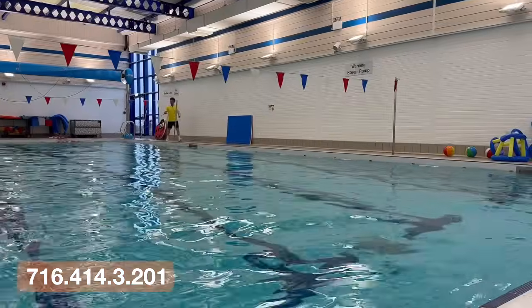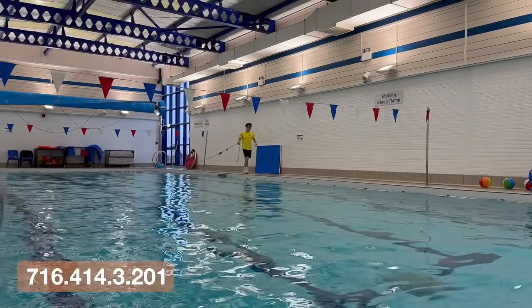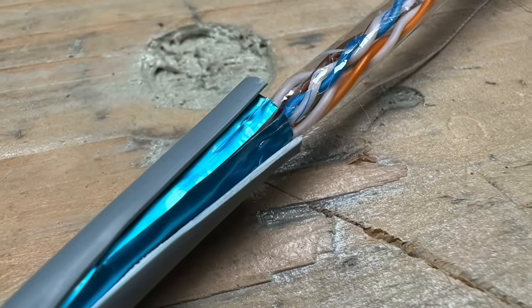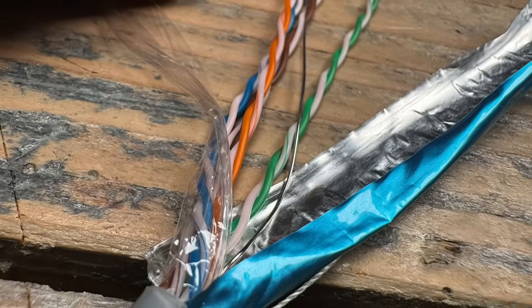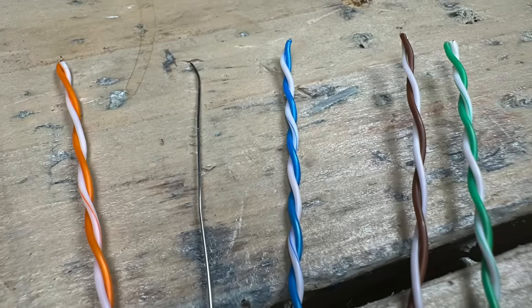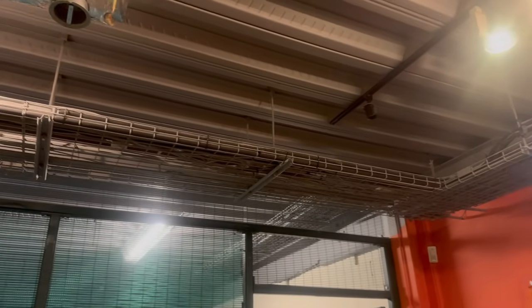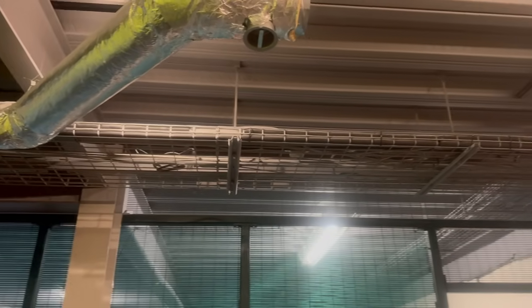Regulation 716.414.3.201 prohibits the use of SELV or PELV sources for ICT cabling in certain special locations. This includes bathrooms, swimming pools, saunas, and locations with restrictive movement. So even though the voltage is low, the environment still matters. There is also a functional earthing aspect. The cable screen may provide a form of functional earthing, but it is not suitable as a protective conductor, so it cannot be relied upon for fault protection. So the key change here is that data cabling is no longer just about communication. It is now part of the electrical installation, and it needs to be selected and installed with that in mind.